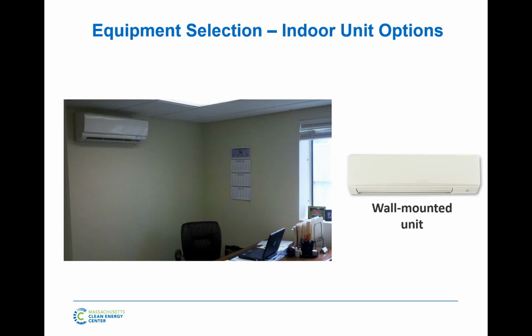But because these aren't pushing through ductwork, these are the most efficient units out there. The downside is that these are the one type of unit that has no way to integrate ventilation air directly. When JS talks about ventilation air, one of the options he's going to go over is how it can be integrated directly to the system. These units have no way of ducting the ventilation air to the wall mount unit. You have to introduce it directly to the space, near the unit, or by some other detached method. That's the one downside, there's no way to bring that ventilation air directly to them.